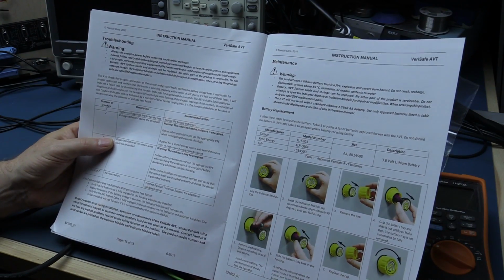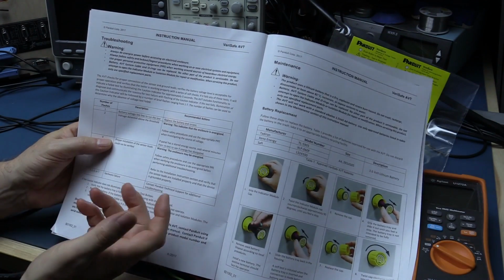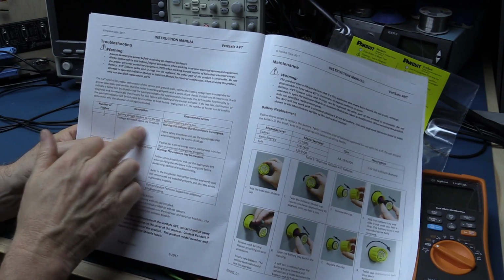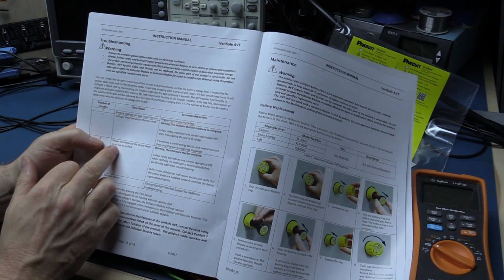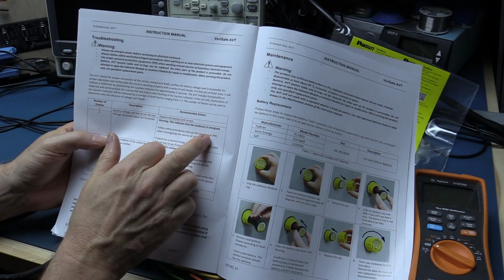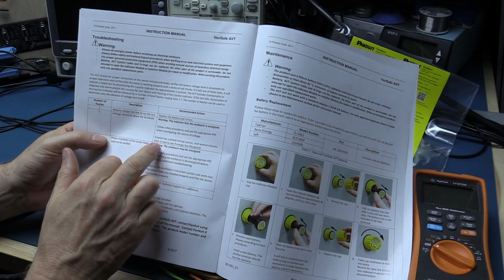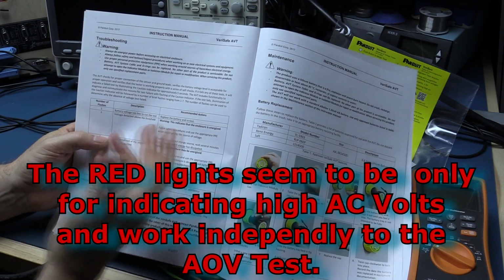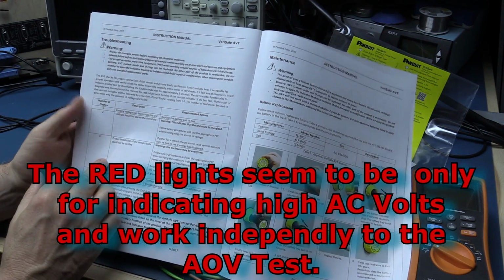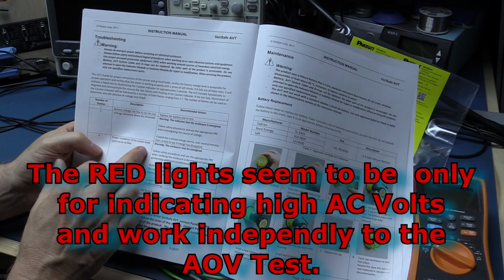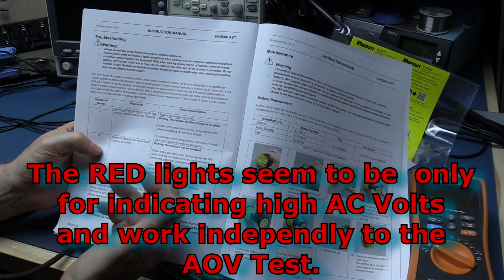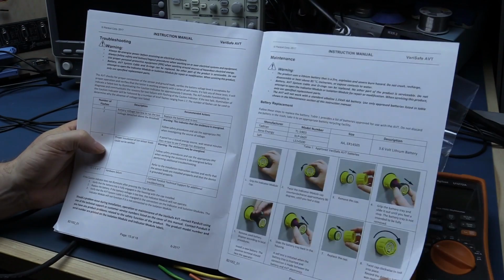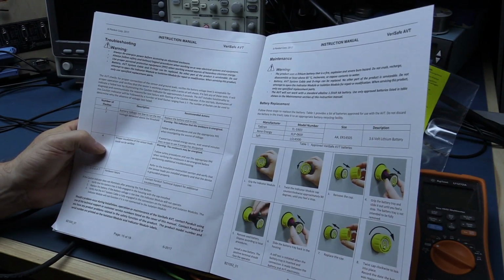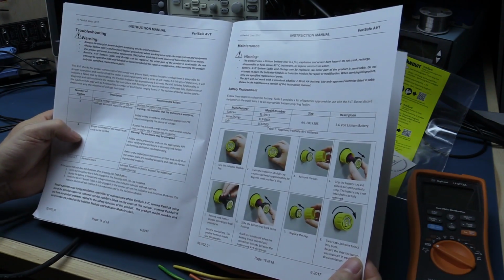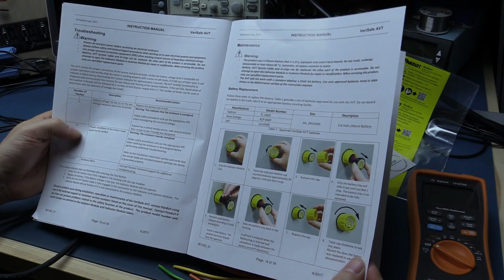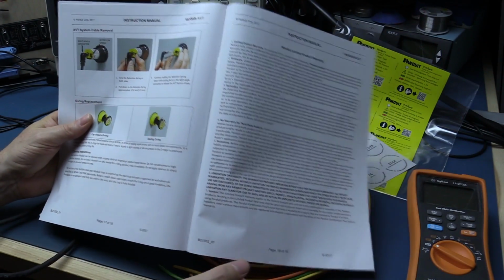A few troubleshooting tips for wiring, warnings and things. Battery voltage low - replace it. So if you don't get any indicators, you replace the battery. Voltage detected above the threshold, you're going to get the red lights. When you turn it off, wait several minutes for any stored energy to dissipate. Proper installation of the sensor leads could not be verified - that will probably also flash the yellow light indicating hardware failure. And of course you need to replace this with a 3.6 volt lithium AA-sized battery. That's pretty much it.